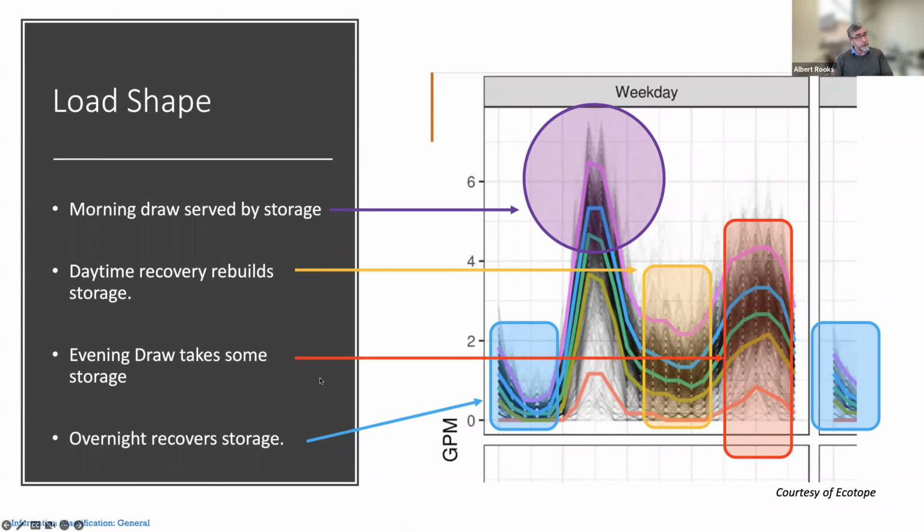We can turn the heat pumps on to start recovering that primary storage. And that primary storage recovery can continue on through the day. Usually by that second peak, we'd like to have the primary storage pretty well recovered.